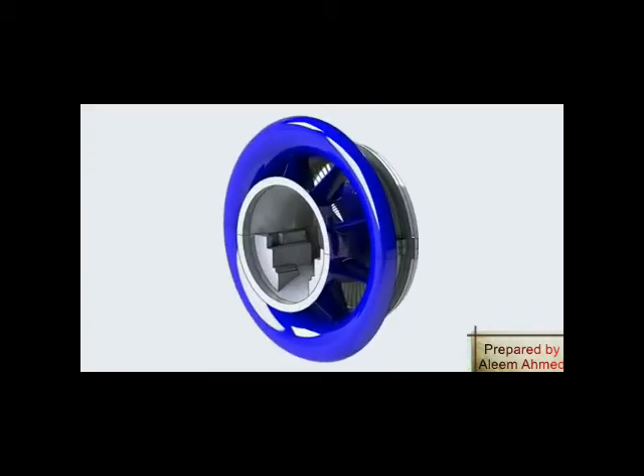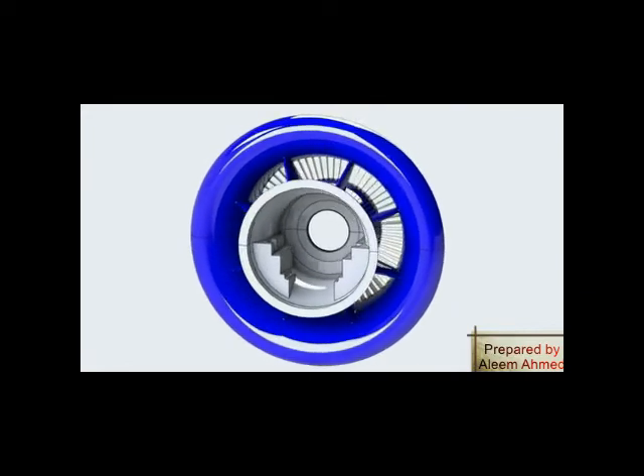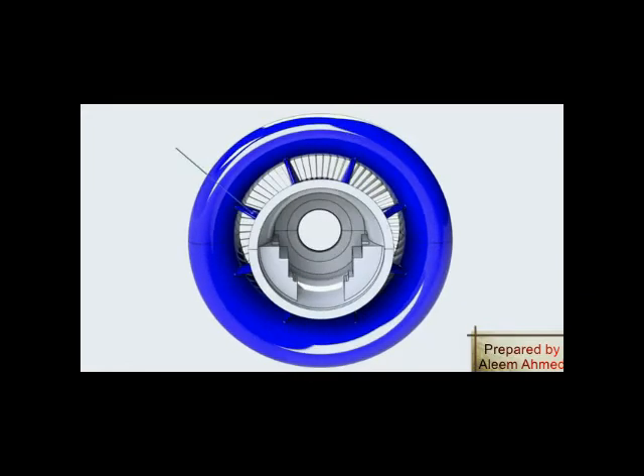The inlet casing is located at the forward end of the gas turbine. The blue painted section at the forward of the casing is called the bell mouth. The inner bell mouth is positioned to the outer bell mouth by eight airfoil-shaped struts. The bell mouth functions to direct air normally and uniformly to the inlet guide vanes for efficient airflow control and better inlet flow coefficient.